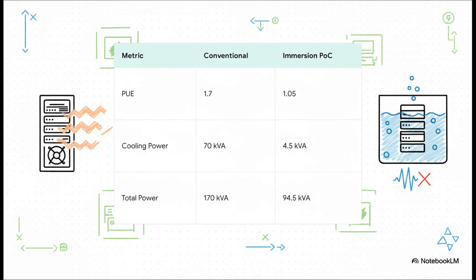A typical data center might have a PUE of 1.7 and use 70 kilovolt amps just for cooling. The KDDI system achieves a PUE of 1.05 using just 4.5 kVA. The overall power savings are massive.